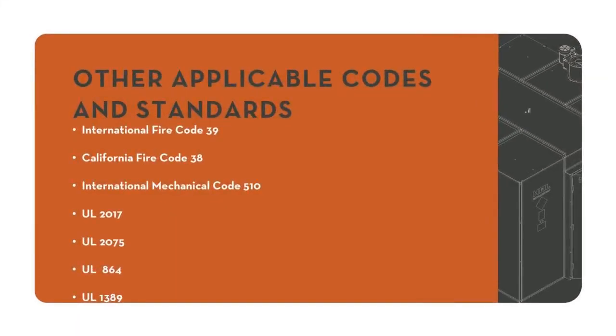Here are other applicable codes that are not NFPA codes. They are the International Fire Code and California Fire Code, which are pretty similar. So again, at the beginning of that one, they'll call out that 25% threshold. You cannot go over that. And then within this code, they call out certain standards for sensors and control units. So UL 2075 is called out within IFC and CFC for a sensor rating. So your sensor has to be up to that UL 2075 standard per IFC.